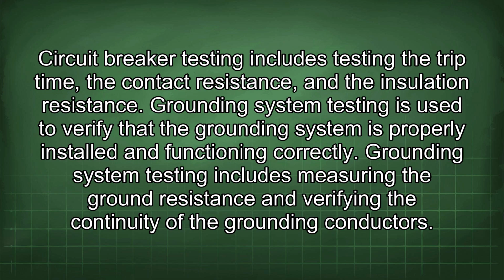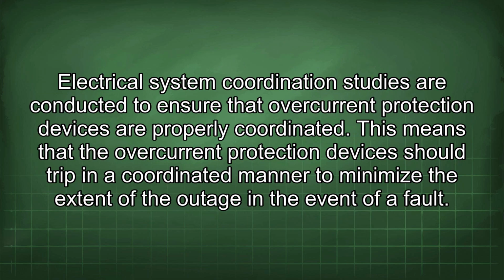Grounding system testing includes measuring the ground resistance and verifying the continuity of the grounding conductors. Electrical system coordination studies are conducted to ensure that overcurrent protection devices are properly coordinated. This means that the overcurrent protection devices should trip in a coordinated manner to minimize the extent of the outage in the event of a fault.